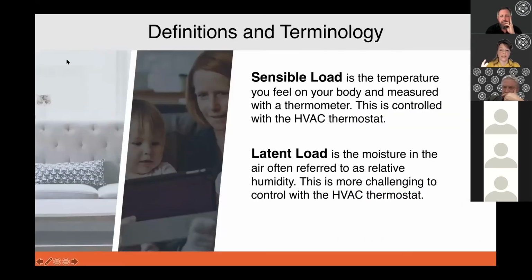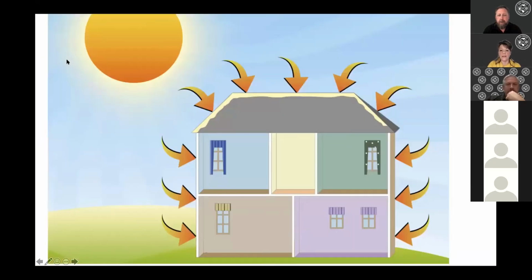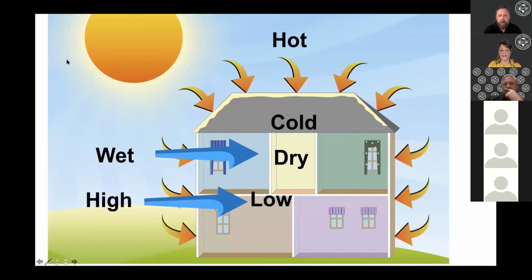Just so we understand going through this, some basic terminology: sensible load is the load the thermostat is trying to get to, that's the temperature we feel. The latent load is the moisture in the air. We often count on our air conditioner to handle both, but we're seeing more challenge with moisture loads. Especially in this climate in the Carolinas, hot goes to cold, wet goes to dry, and high goes to low.